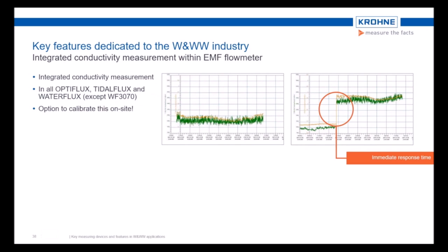The charts show the comparison of the accuracy of an inductive analytical measurement, orange curve, with the performance of the conductivity indication measurement of the EMF integrated conductivity, green curve. You see that the basic accuracy of an analytical sensor cannot be reached, but the accuracy to monitor the values is absolutely sufficient. Fast value changes can be detected immediately. Furthermore, the signal can of course be flattened by using an output compensation.